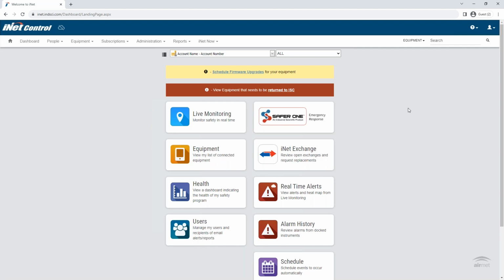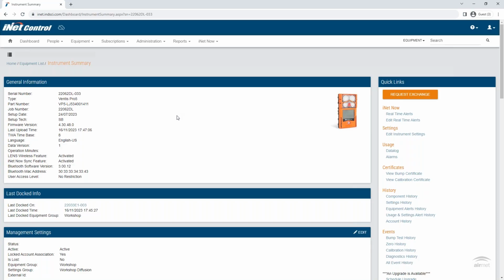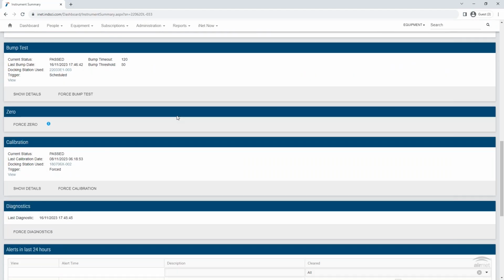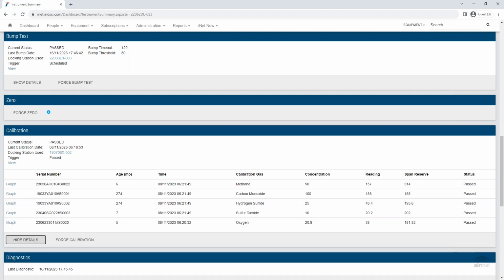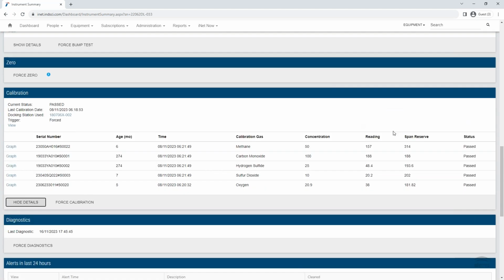To view the span reserves of sensors on an instrument, first log into iNet Control. Then enter the serial number of the instrument in the search box in the top right and click Search. Scroll down to the calibration section on this page and click Show Details. This will show all the sensors the instrument is equipped with. The span reserve results of the latest calibration will be shown here. Typically, a span reserve of 75 or greater is considered a healthy sensor.